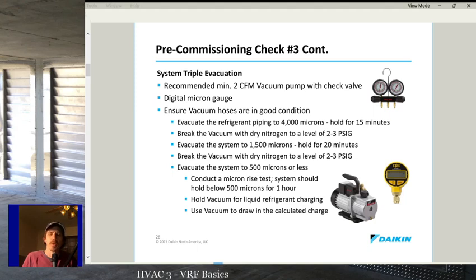But if you can hold below 500 for an hour, you're pretty good. You have very few leaks. Again, you're always going to have some leaks, but you'll have very few. You should be in good shape. The system is tight and dry, and you're good to go. If you get the habit of doing that on every system you service or install, you should have very few issues when it comes to system operation. You'd be surprised what just a tight, dry system can do for the quality of the install.